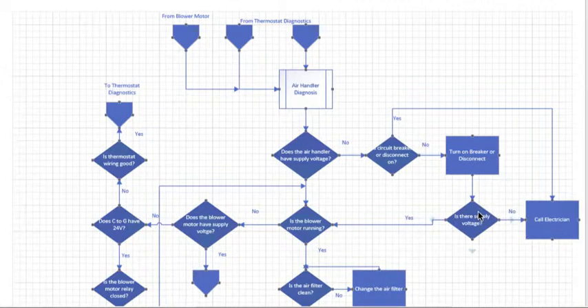Once you have supply voltage, the next thing you want to do is check to see if the blower motor's running. Remember, when you did your thermostat diagnostics, where you started off this whole process, we had you either jump out or turn the thermostat fan switch to on from auto. So the blower motor should be running at this point. If the blower motor is not running, find out if the blower motor has supply voltage. Easy to do: take a meter, check the leads. Does the motor have supply voltage?